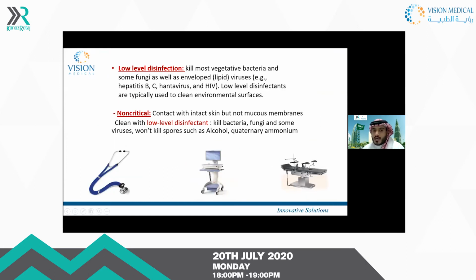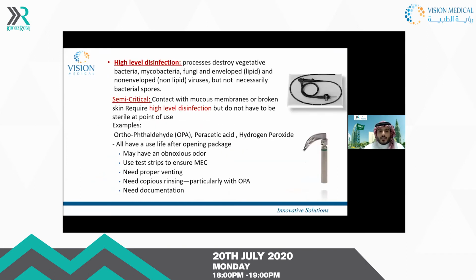Now we are talking about high-level disinfection. This destroys vegetative bacteria, mycobacteria, fungi, and enveloped and non-enveloped viruses. We can use this for semi-critical items, which contact mucous membrane or broken skin, but we don't have to reach the sterile point of use. Like OPA, which most of us working in CSSD or the endoscopy unit are using, and peracetic acid, hydrogen peroxide, and this is some of the advantages or needs assessment for these chemicals.